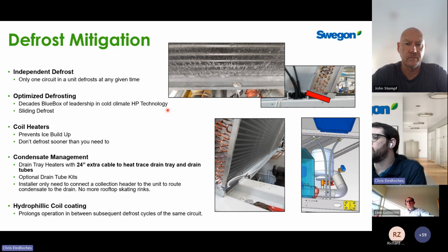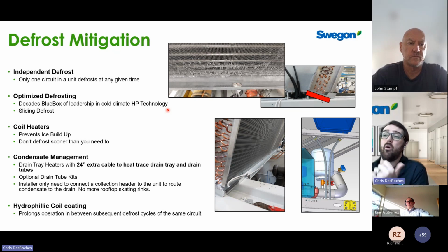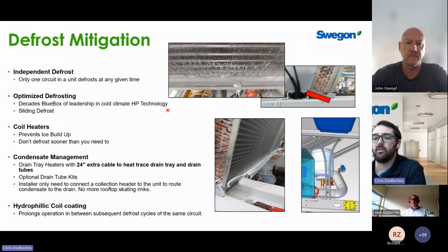So the concern with this is typically if it's warm outside, but it's very humid, if you're only defrosting on pressure, you could actually wait too long before starting a defrost cycle by allowing too much frost and ice to accumulate on the coils. Or on the other side, if it's very cold but dry, we could actually be going into defrost mode without actually having ice and frost on the coil. So the sliding defrost just allows us to basically tune it to your local conditions to find that balance between not defrosting too frequently and having acceptable efficiencies by not allowing too much frost to build up on the coils.